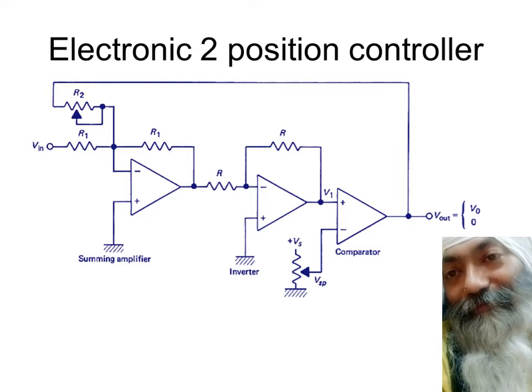It may remain on for a good 10 minutes or 15 minutes. And only when it becomes 24 should it turn off. So instead of turning on and turning off at exactly 25, we give a good amount of space between turning on and turning off. This space is called neutral zone. Neutral zone means that in this neutral zone, at the temperature 25 degrees Celsius, when it was cooling down and AC was on, it will remain on.